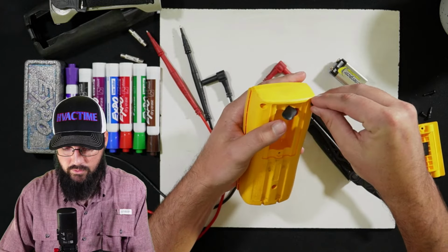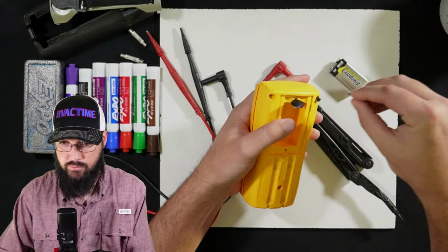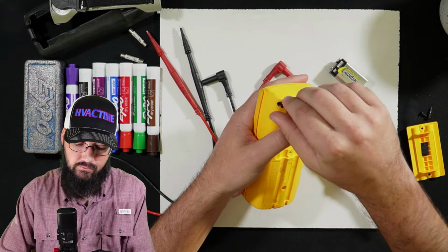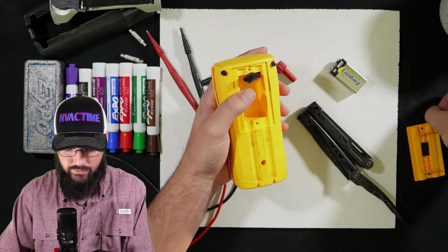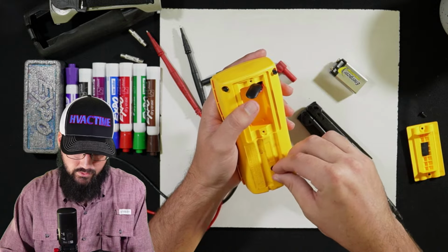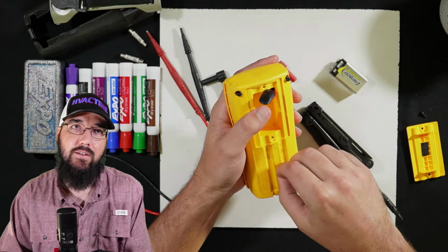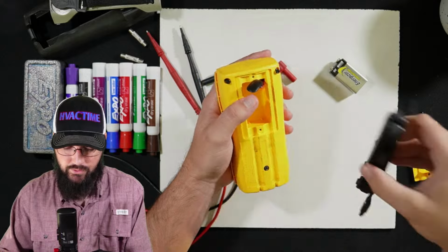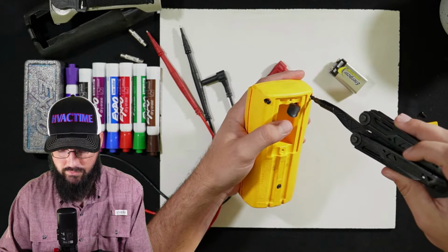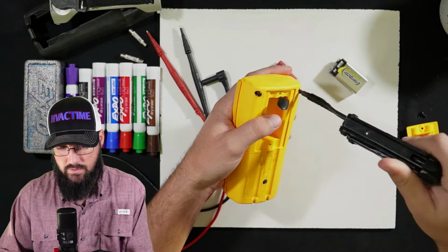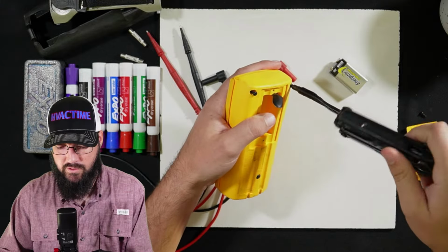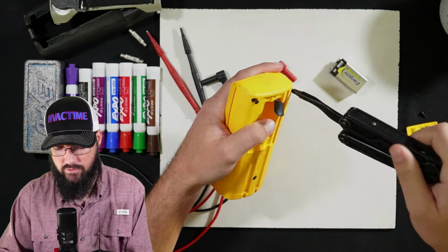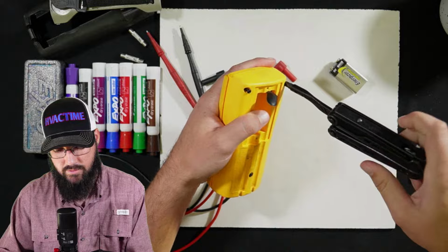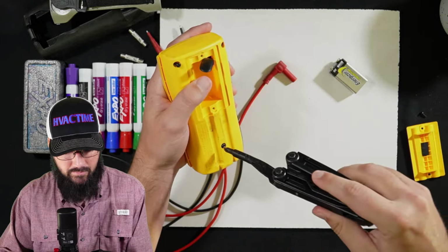But you start getting into chiller drive troubleshooting, most of those are between 10 and 20,000 microfarads, where most of those are that I've worked on. So, do you know what the max is for that meter? I can look it up here in a minute. If not, I'm just curious.